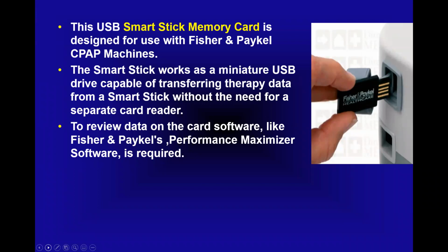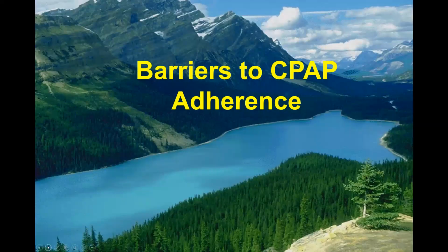Another, just building on this theme a little bit more, USB smart stick memory card, is designed for use with, again, Fisher and Paykel. I'm not promoting Fisher and Paykel, just one example. Smart stick works as a miniature USB drive capable of transferring therapy data from the smart stick without the need for a separate card reader. And then to review the data, you just need matching software, and there are different softwares, but typically you're matching the hardware with the particular software as well. So let's drill down a little more on some of these barriers.